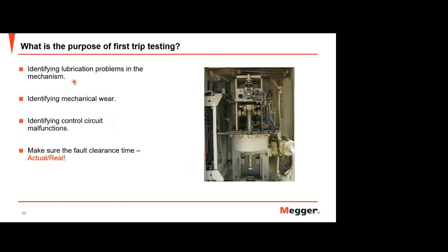investigation. So in 1997, a certain Californian utility implemented a maintenance strategy that included lubricating circuit breaker bearings with some grease material. In that document, they mentioned that lubrication has to be considered in the maintenance of your circuit breaker, because it can affect the operation and the performance of the circuit breaker. So with first trip testing, we can identify lubrication problems in the mechanism.